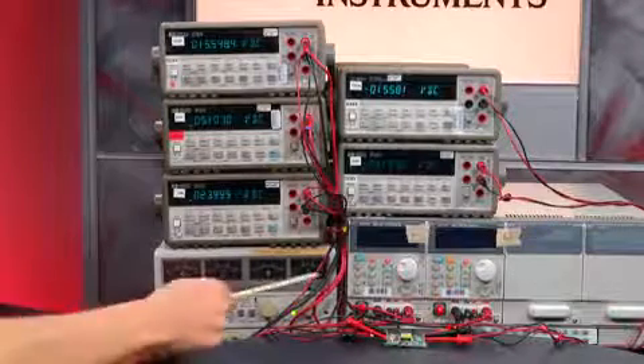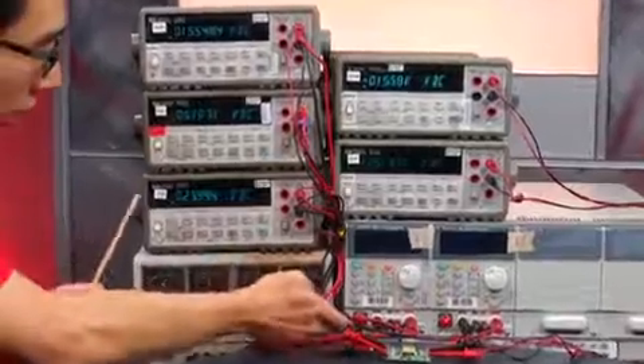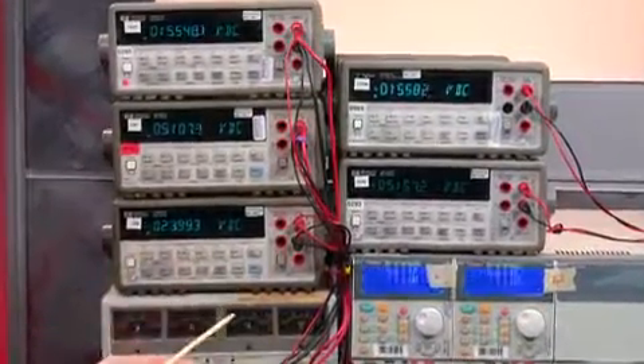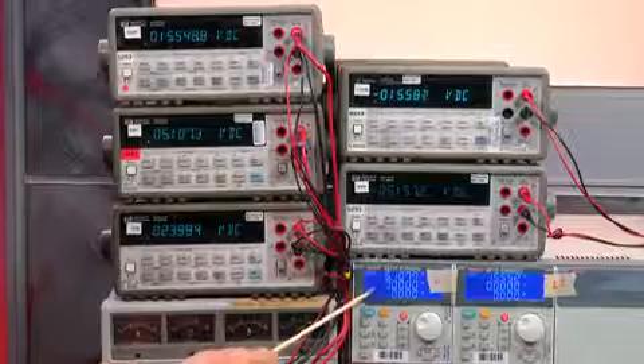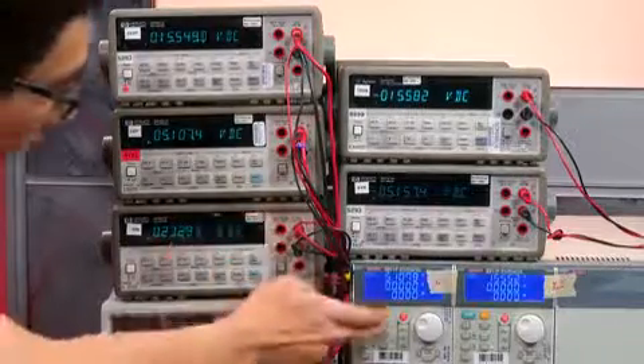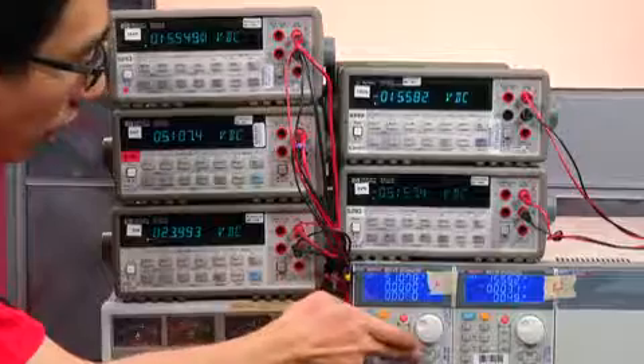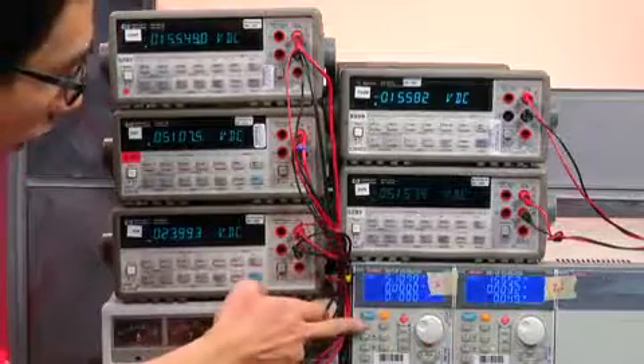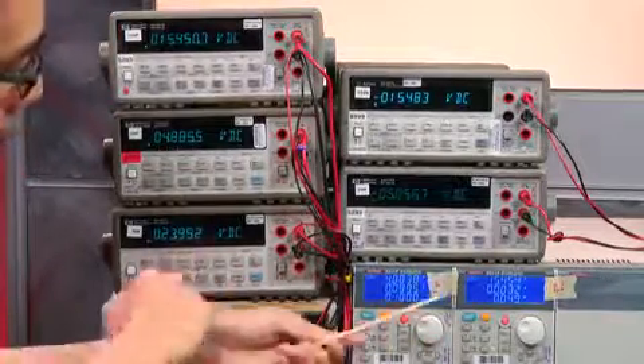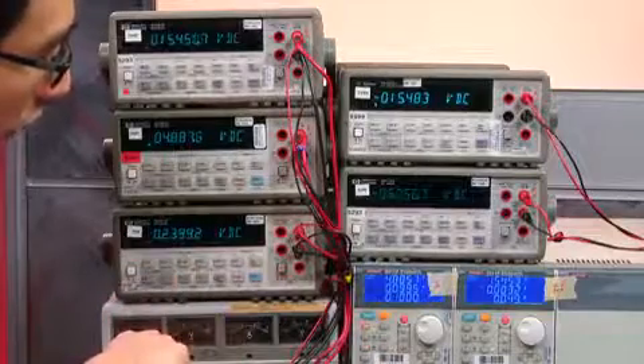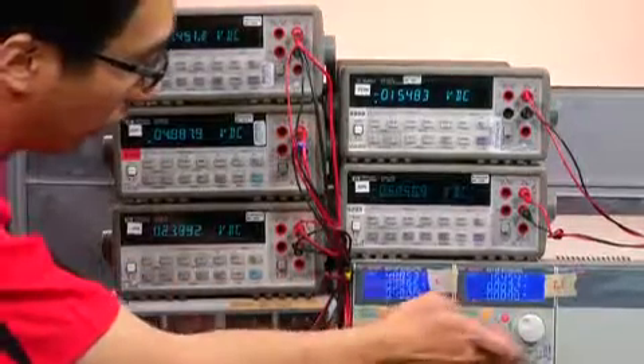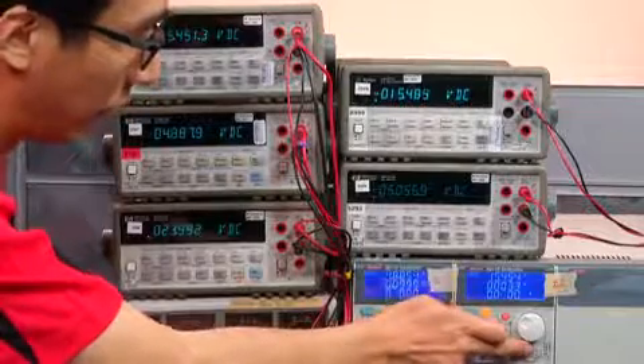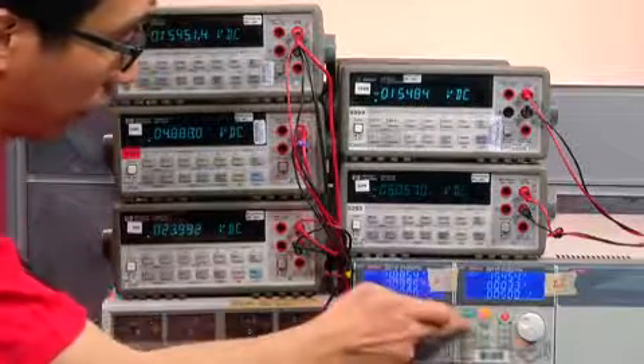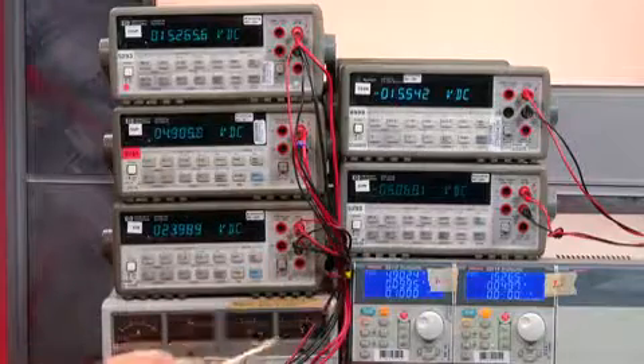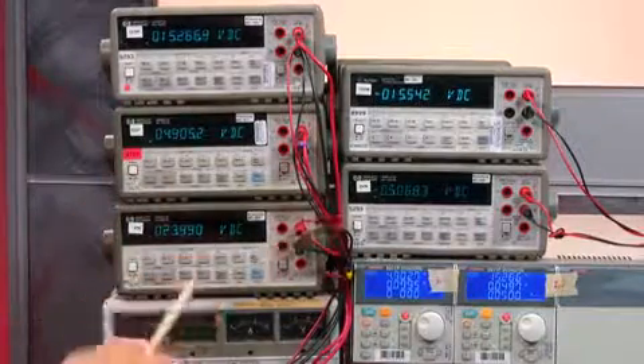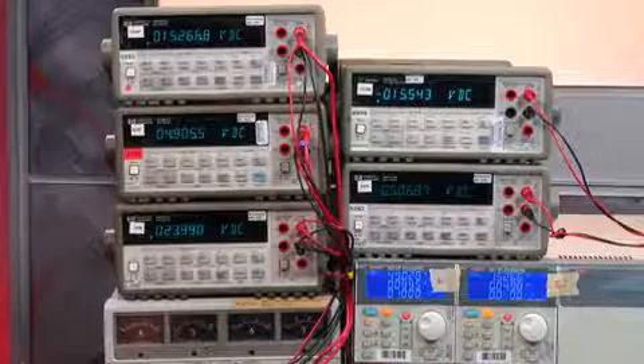We also connected an electronic load. Let me turn this on. This channel is connected to the 5 volt output—I'll set the load at 100 milliamps and turn it on. The other channel is connected to the 15 volt output—I'll set the current at 50 milliamps and turn it on. Now both loads are on, and all 4 outputs remain stable.